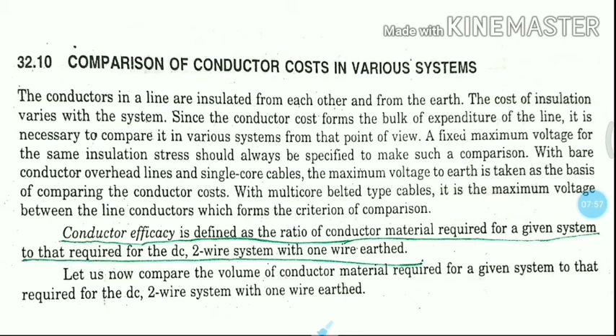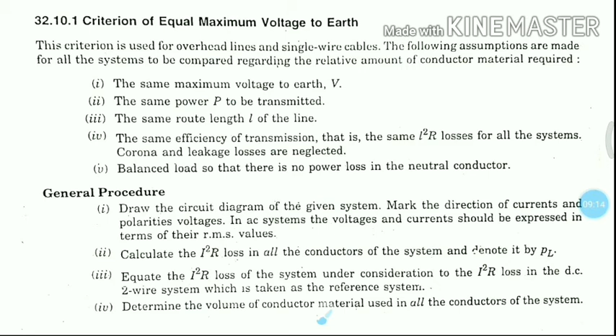Let us now compare the volume of conductor material required for a given system to that required for a DC two-wire system with one wire earthed. Criterion of equal maximum voltage to earth. This criterion is used for overhead lines and single-core cable. The following assumptions are made for all systems to be compared. Number 1: the maximum voltage to earth is the same. Same power P to be transmitted. The same route length of the line. Same efficiency of transmission, that is, the same I squared R losses for all the systems. Balanced load so that there is no power loss in the neutral conductor.